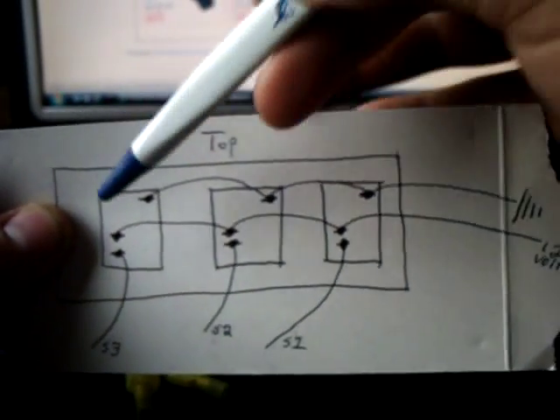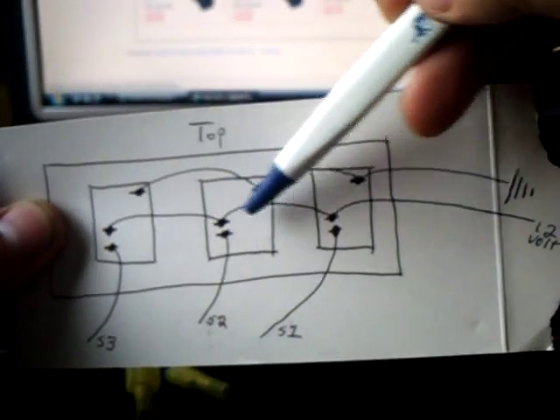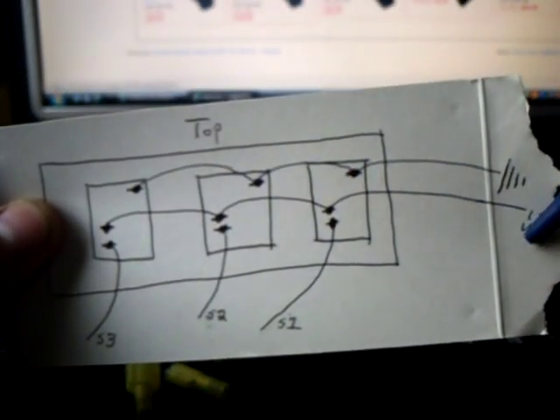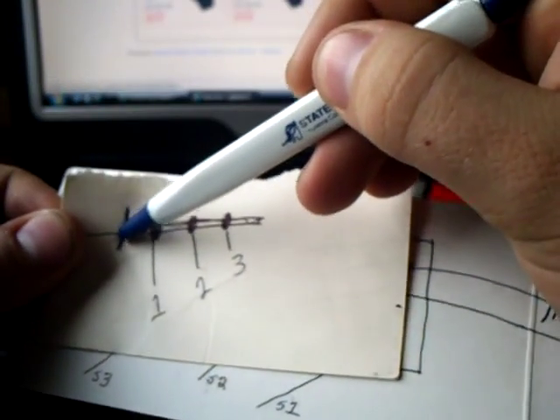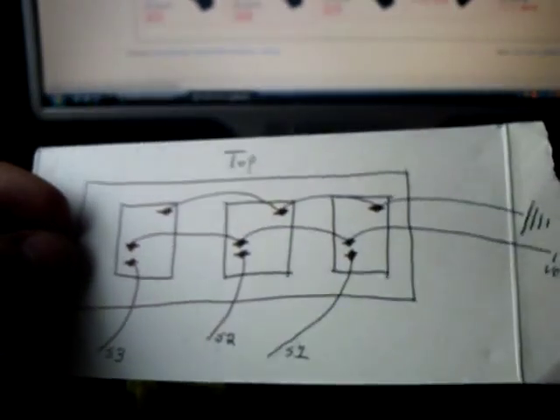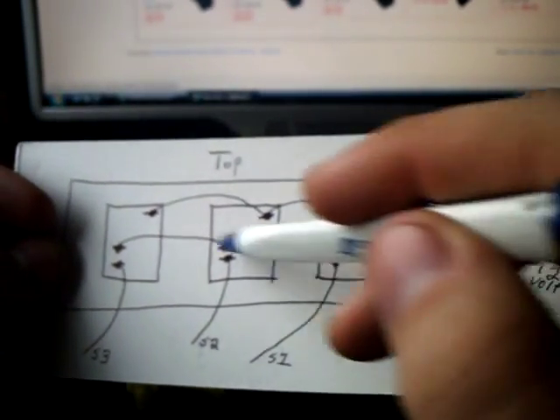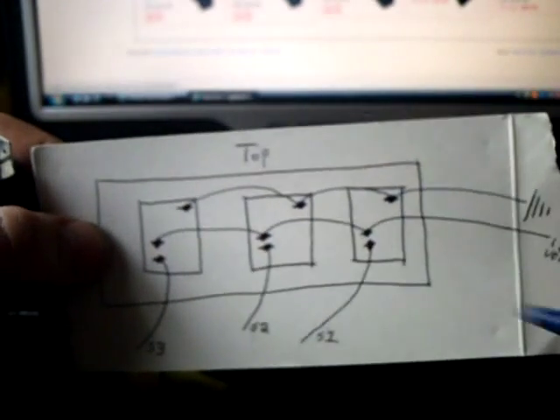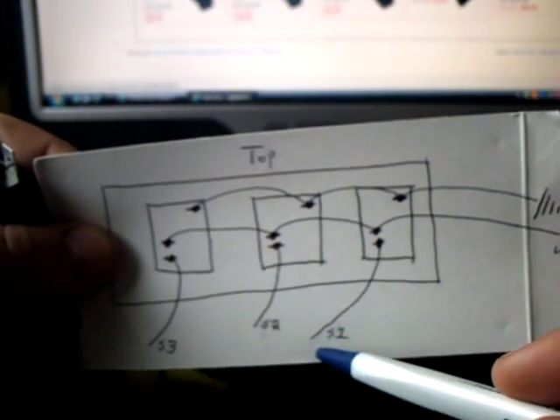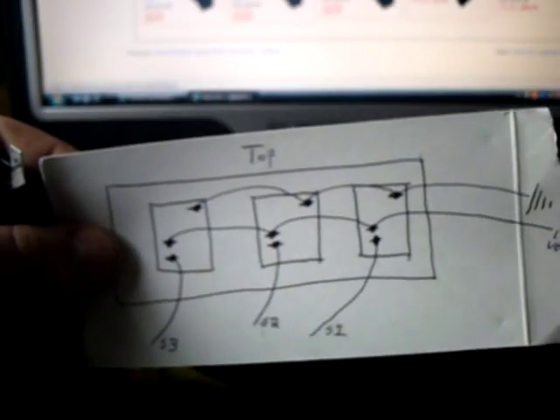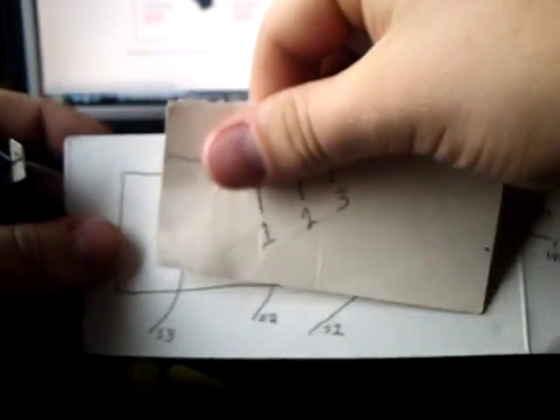I'm going to do the same exact thing with my power. One, two, three, to the pre-existing power wire that was already going to this switch right here. So this power wire is just being extended to the switch box, and then going to all those. And then it's going to be three separate wires for switch one coming off corresponding to number one on here, switch two on here, which corresponds to number two on here, and switch three corresponding to wire three on here.